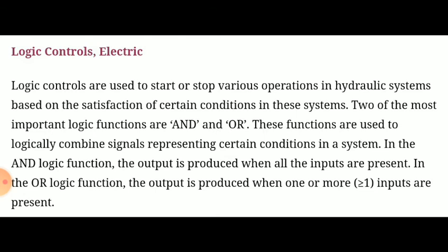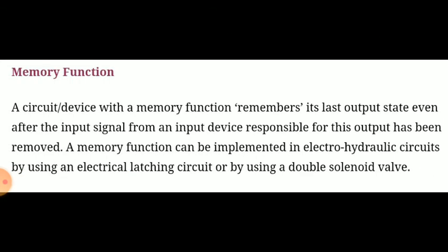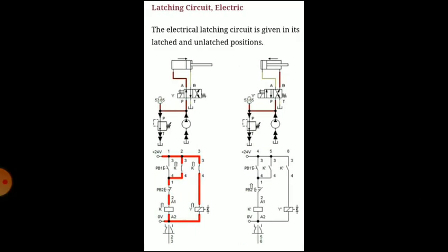inputs are present. Then memory function. A circuit or device with a memory function remembers its last output state even after the input signal from the input device responsible for this output has been removed. A memory function can be implemented in electrohydraulic circuits by using an electrical latching circuit or by using a double solenoid valve. So you can see the latching circuit.